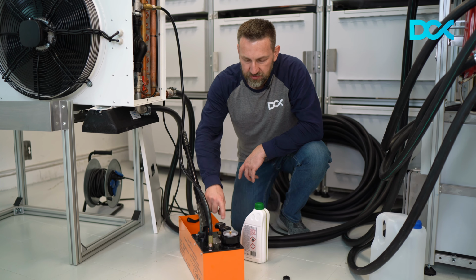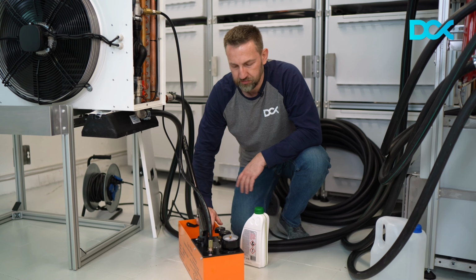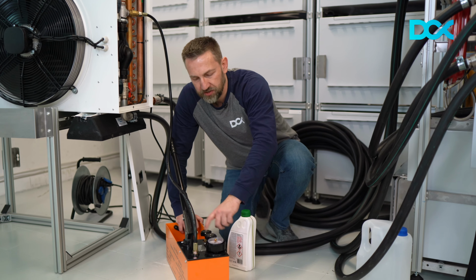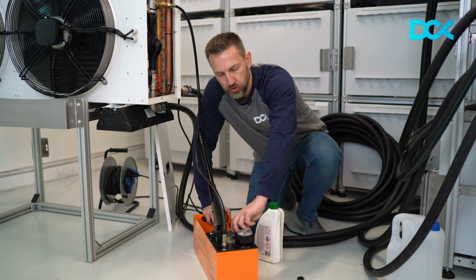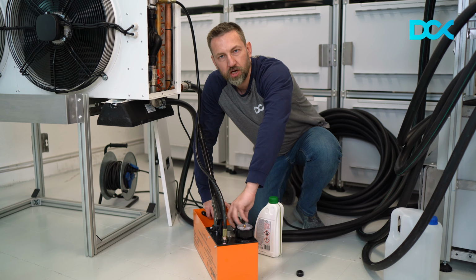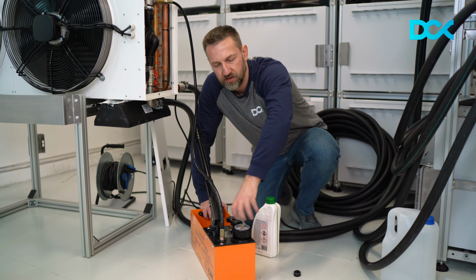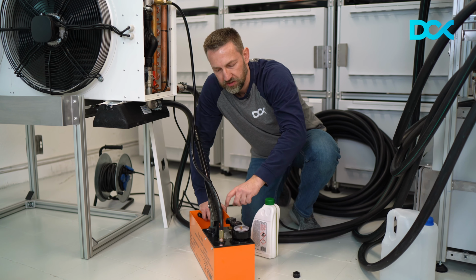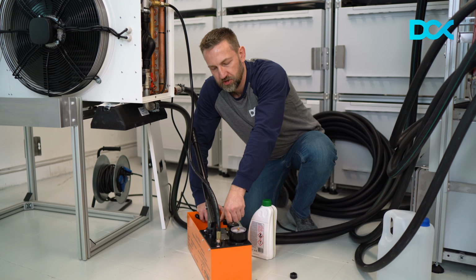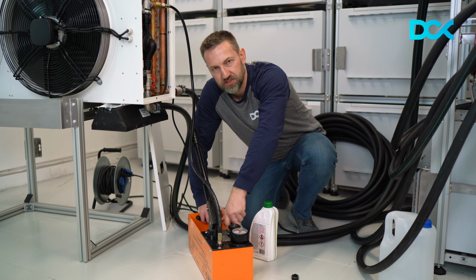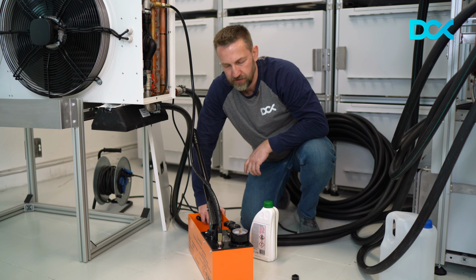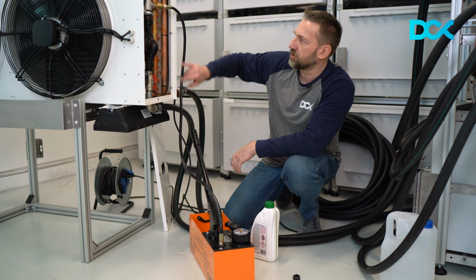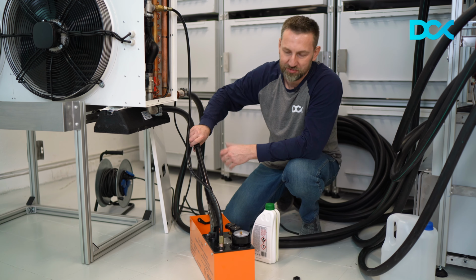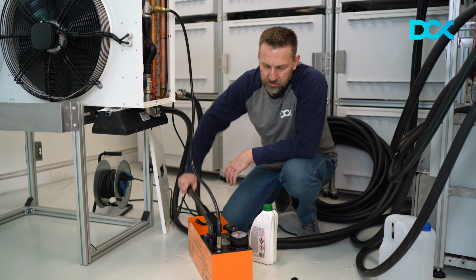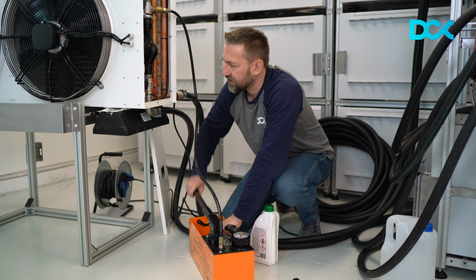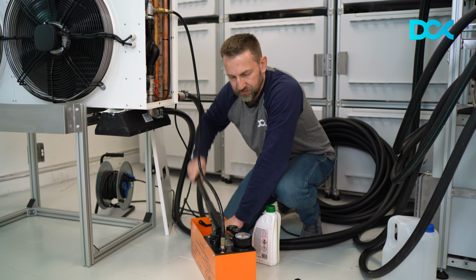Then you have two valves here. It's a very simple tool to start. Valve 1 and valve 2. Valve 1 should be open completely, so counterclockwise, completely open to the left. All right, and valve 2 should be closed completely, so to the right, clockwise. All right, now I close it, and now I will pressurize the loop. So basically I will do it manually. It will take some time, but not too much. So I'm just using the lever and adding the fluid into the system.